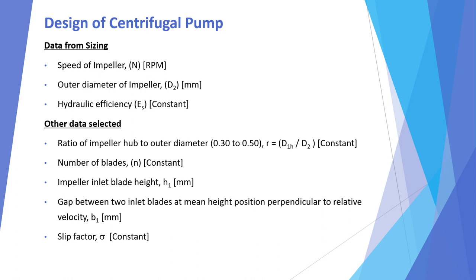The ratio of impeller hub or root diameter to outer diameter, r = D1h / D2, typically varies from 0.3 to 0.5. The number of blades N can be 4, 5, 6, 7, 8, 9, or 10. The impeller inlet blade height H1 is selected, as is the gap between two inlet blades at mean height position perpendicular to the relative velocity, B1 in mm. A slip factor sigma is also selected. These are the design-selected values.